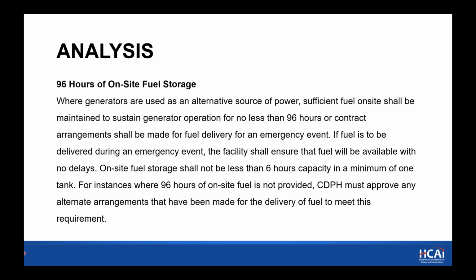What we've added in is on-site fuel storage shall not be less than 6 hours capacity in a minimum of one tank. For instance, where the 96 hours of on-site fuel is not provided, CDPH would need to approve any alternate arrangements that have been made for delivery of fuel to meet this requirement. So based on the bill, if an acceptable plan is submitted, then you would need to have 6 hours on site with 90 hours delivered.